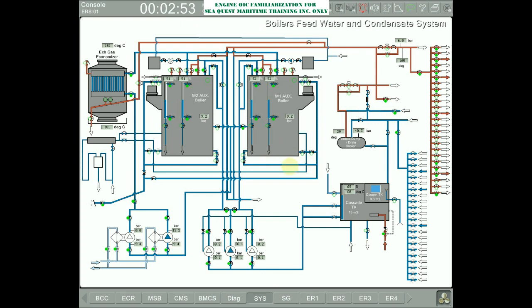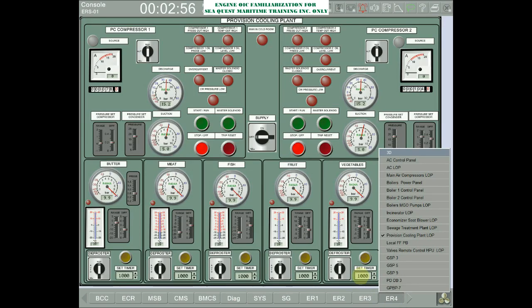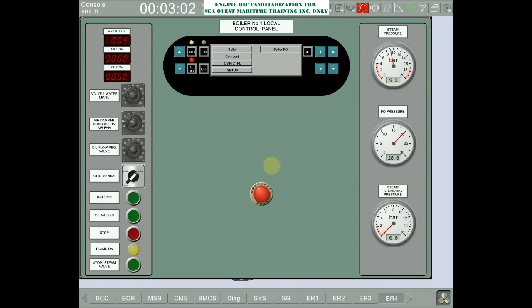Afterwards, go to ER4, select number 1 boiler control panel and acknowledge the alarm. Press the alarm reset button and then put the auto manual selector knob to auto and press the on button so that both auto and on buttons are on.